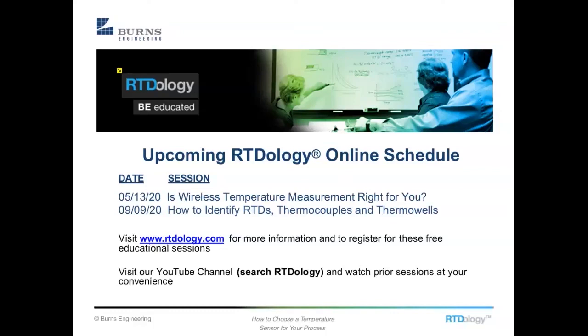Yeah, there are some products out there that are calling themselves smart sensors, along the lines of this question. Really, the sensor itself isn't what is smart. It's the electronics that you put on top of the sensor. For the most part, the sensor does what it does, and usually it's in the transmitter, or there's some additional electronics built in on the top of the sensor, similar to a transmitter, where it's doing some type of compensation or comparison. In some cases, you may have two elements down in the sensor, and it's continually monitoring one element while the other element is doing the measurement. And if there's an offset between the two, then it gives you an alarm that says, hey, go ahead and check this.